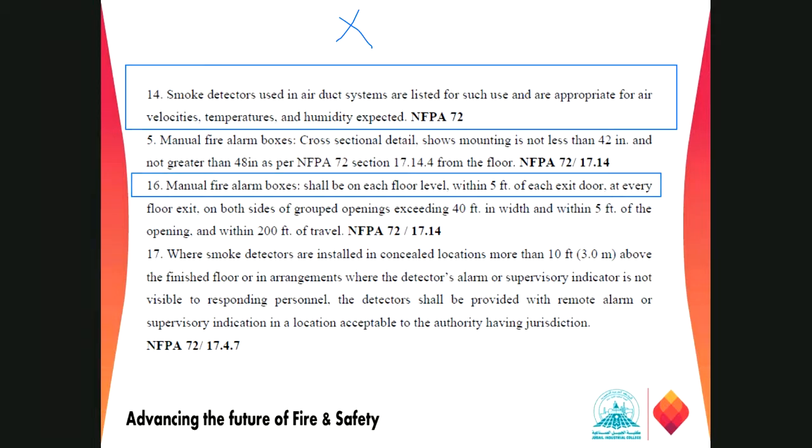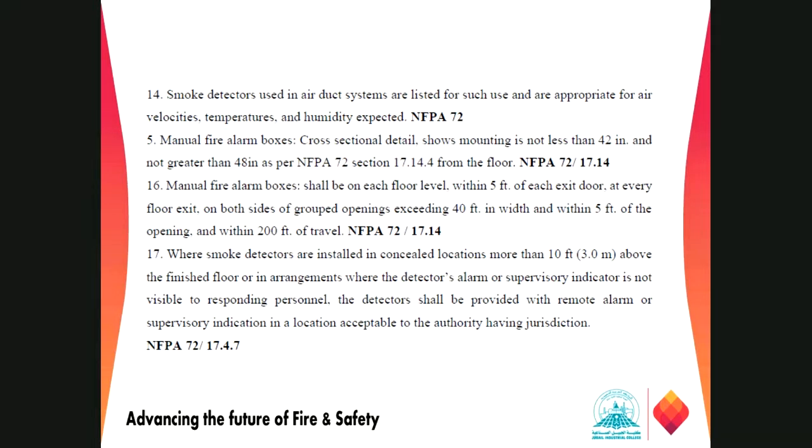And if this is an exit, right, and the width of the exit is 40 feet, the dimension is 40 feet, then in that case, if it is a big exit, more than 40 feet, we need one manual call point at this location and one manual call point at this location, and that should be within 5 feet from the door on both sides, if the width is higher than 40 feet.